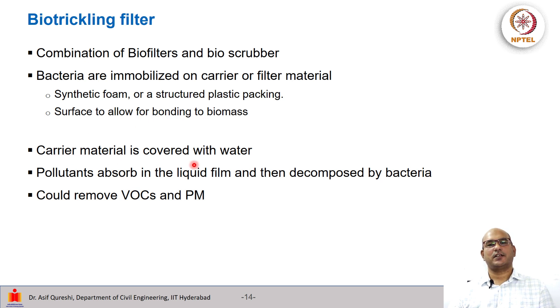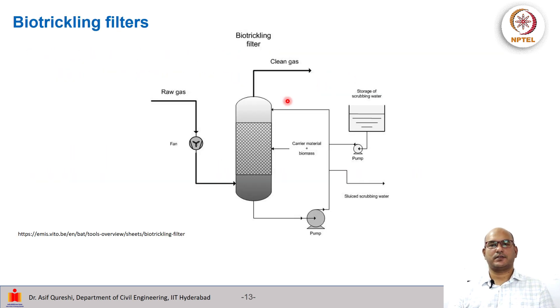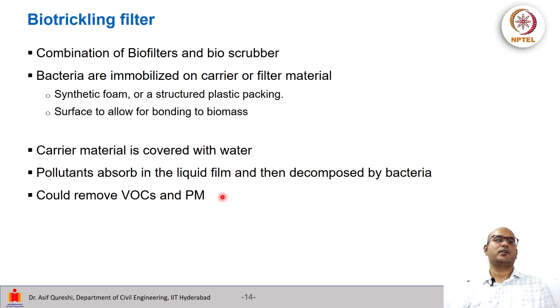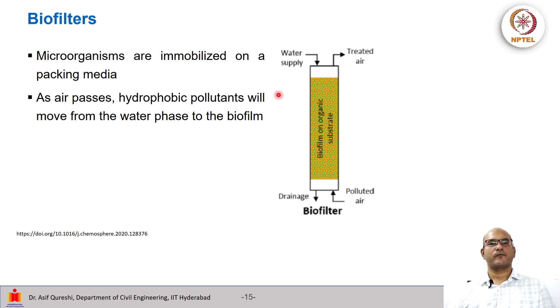The carrier material is covered with water falling from top to bottom. The pollutant absorbs into the liquid film and is then decomposed by the bacteria. In principle this could remove VOCs and particulate matter, but we need sufficient contact time so the compound can absorb into the liquid film and be decomposed by the bacteria. In similar biofilters with immobilized microorganisms, polluted air comes in and as air passes, the hydrophobic pollutant moves from the water phase to the biofilm, which subsequently degrades the pollutant, and treated air comes out.